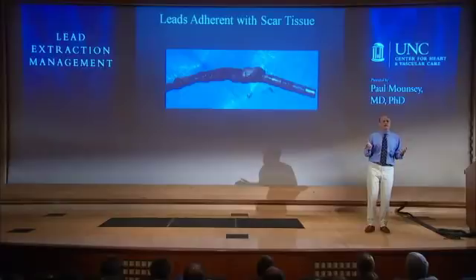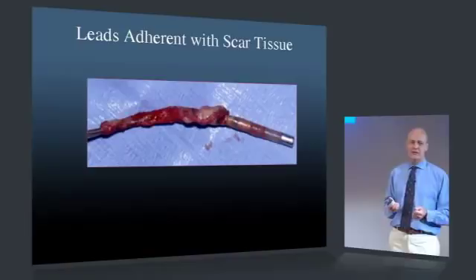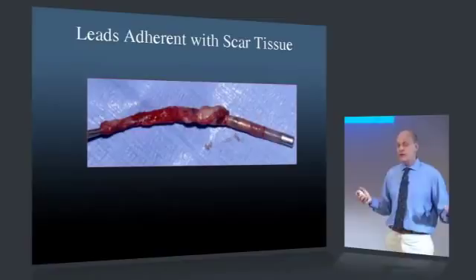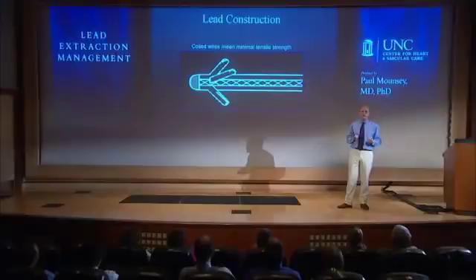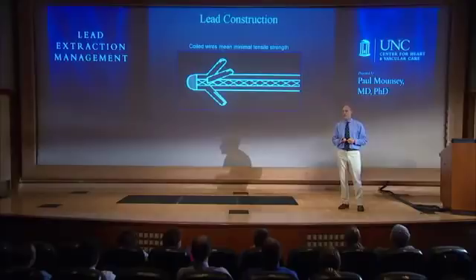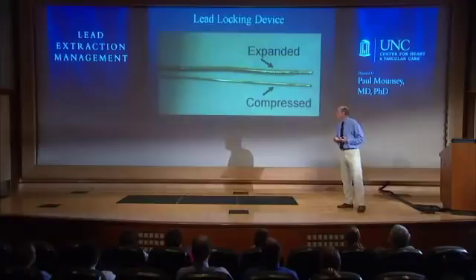The issue with chronically implanted pacing leads is that the lead becomes scarred into the patient. You can't simply open the incision and pull on the lead — if the lead is stuck with scar tissue all the way through the circulation, you need more extreme measures. Pacing leads have very little tensile strength; the conducting wire is coiled, so pulling just unravels the coil. To prevent this, we use lead locking devices — locking stylets with an expandable spring that, when expanded, locks the lead in place so you can exert pull right from the tip.